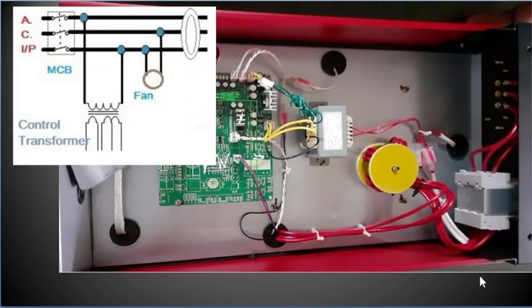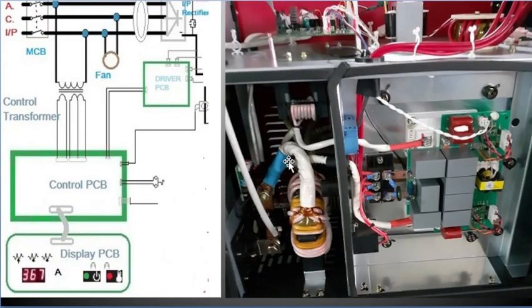Another 3 lines from the MCB are going through an input filter. Output from the filter is going to the lower compartment. The output of the filter comes to a 3-phase rectifier block. It converts AC into DC.